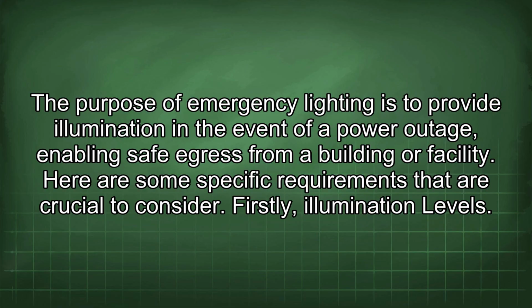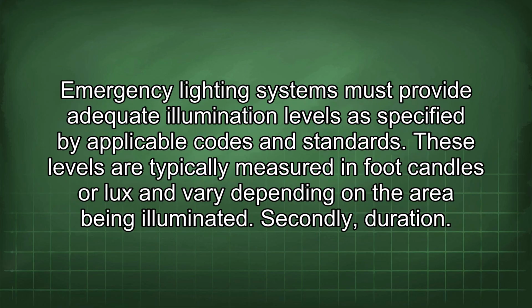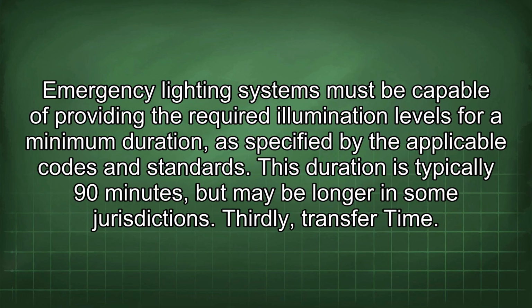Firstly, illumination levels. Emergency lighting systems must provide adequate illumination levels as specified by applicable codes and standards. These levels are typically measured in foot candles or lux and vary depending on the area being illuminated. Secondly, duration. Emergency lighting systems must be capable of providing the required illumination levels for a minimum duration, as specified by the applicable codes and standards. This duration is typically 90 minutes, but may be longer in some jurisdictions.